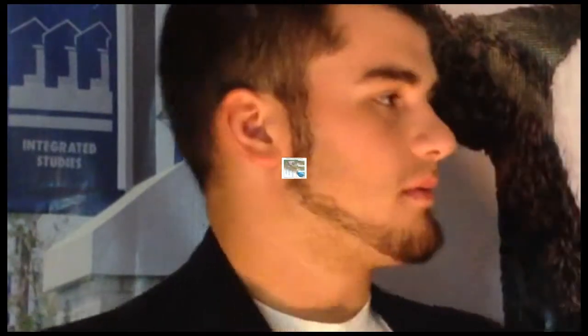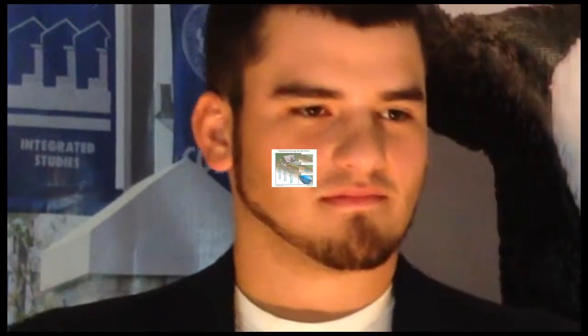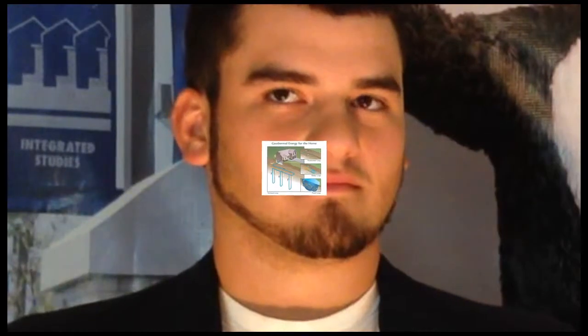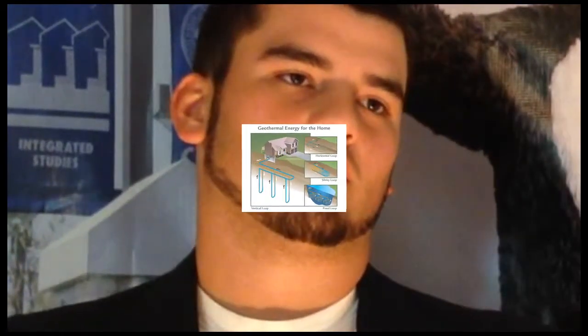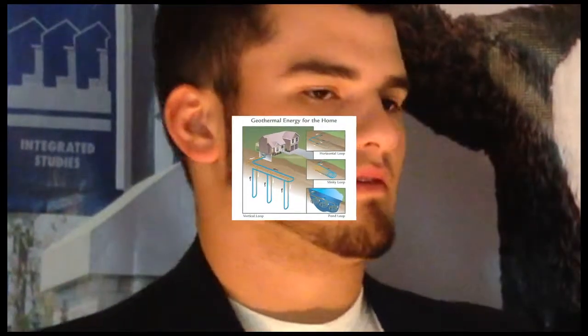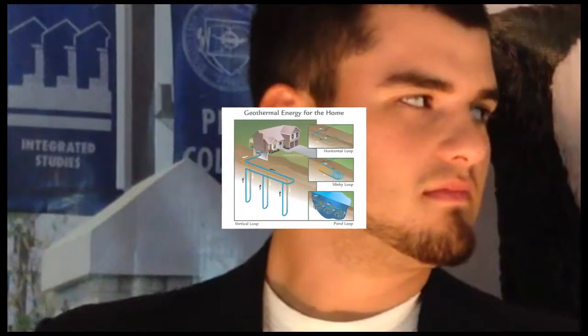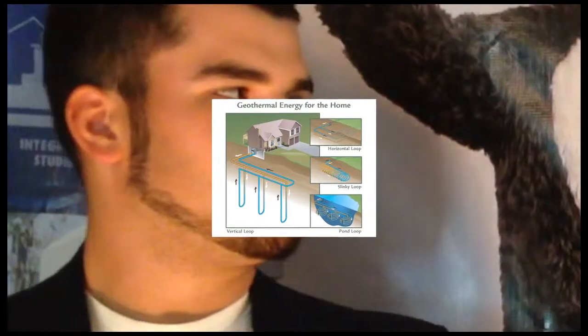What do you feel the biggest difference is between residential and commercial systems? Residential applications typically use a packaged geothermal heat pump which supplies conditioned air through ducting. Also in use are packaged units which supply conditioned water, which can be supplemented by a water heater for radiant floor heating. Commercial systems have a much more complicated design known as a central geothermal system. All the components of this system are separated so that they may be integrated with building automation.